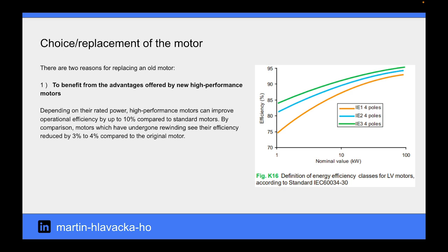The second reason is to avoid oversizing. In the past, designers tended to install oversized motors to provide an adequate safety margin and eliminate the risk of failure even in conditions that were highly unlikely to occur. Studies show that at least one third of motors are oversized and operate at below 50% of their nominal load. However, oversized motors are more expensive and sometimes less efficient than correctly sized motors.